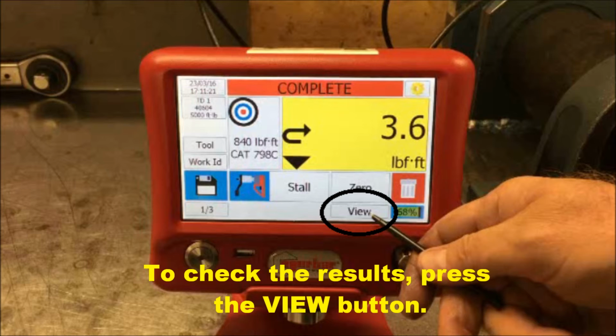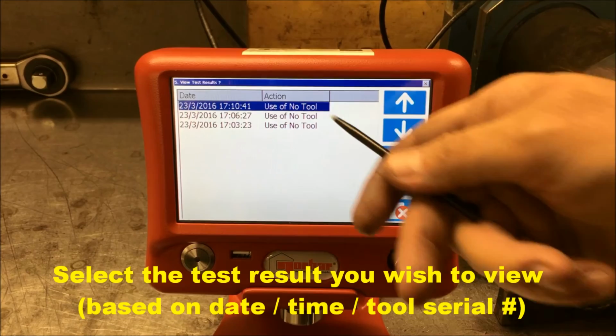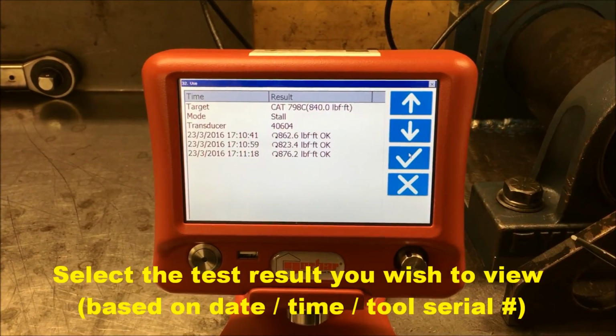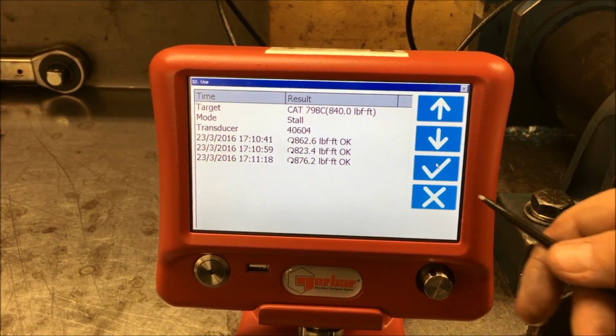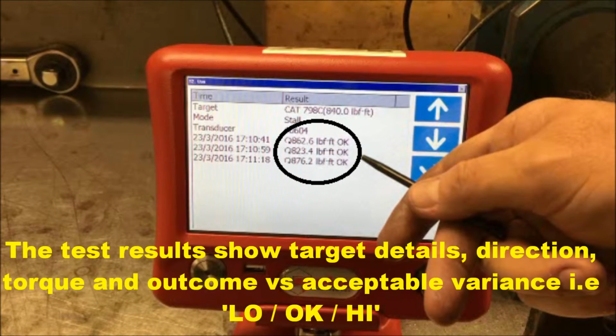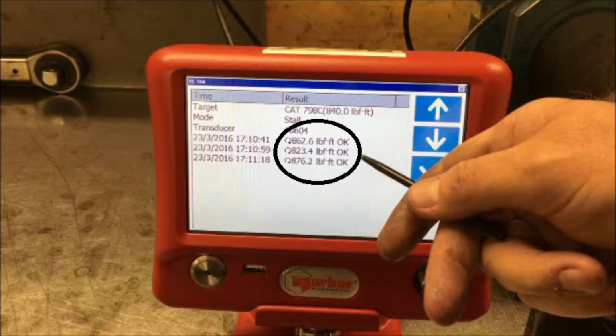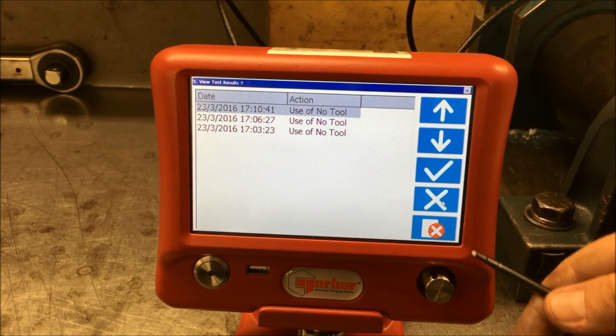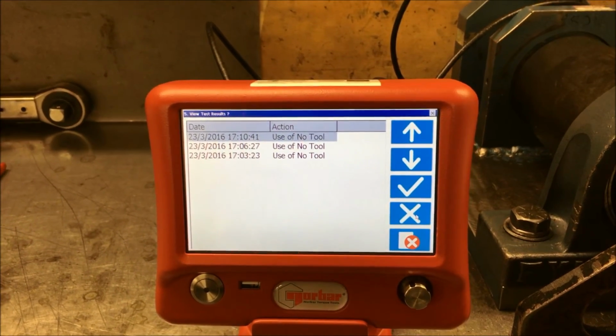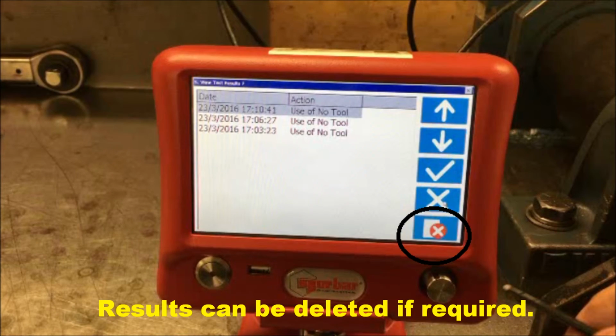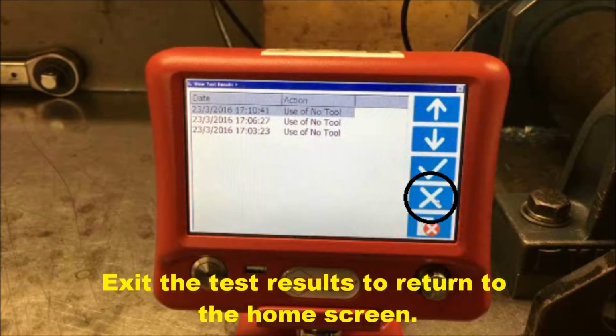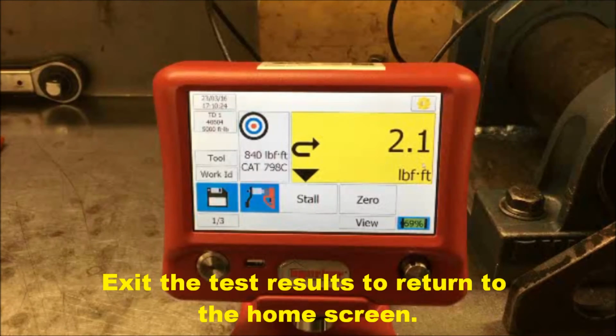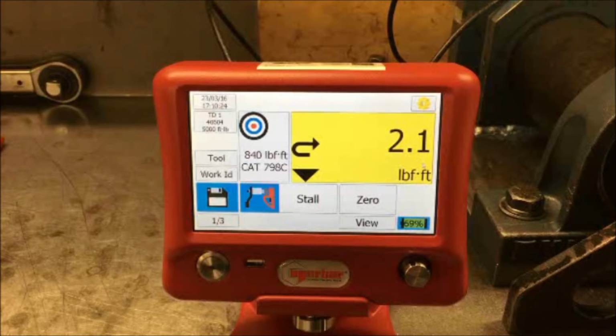To check the results that you have captured, simply click on the View button at the bottom of the screen. Select the last testing that was done by the date and time shown, and there are your test results showing direction of rotation, results, and whether the results were OK, low or high versus the acceptable variance that has been set. Return to the results screen, and if necessary you can delete the results if they are not required. You can exit the results screen and return to the home menu to begin your next set of tests.